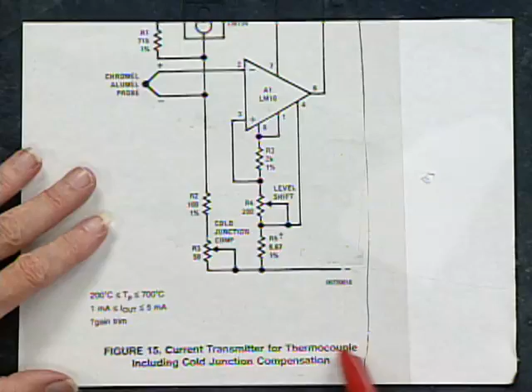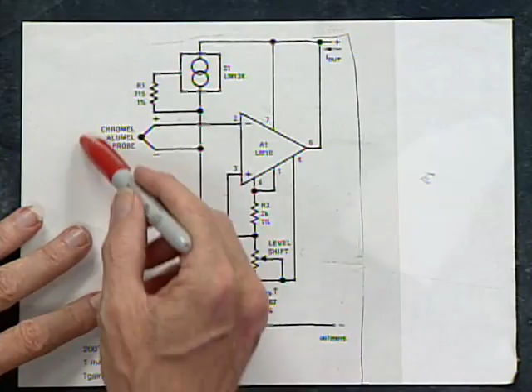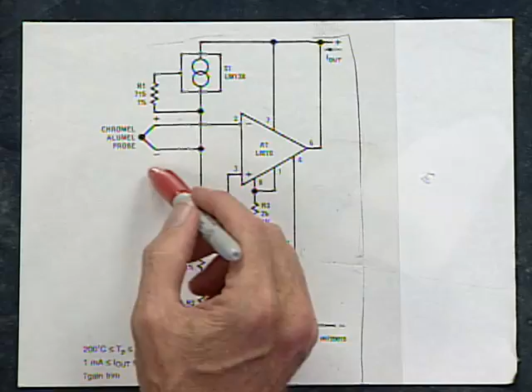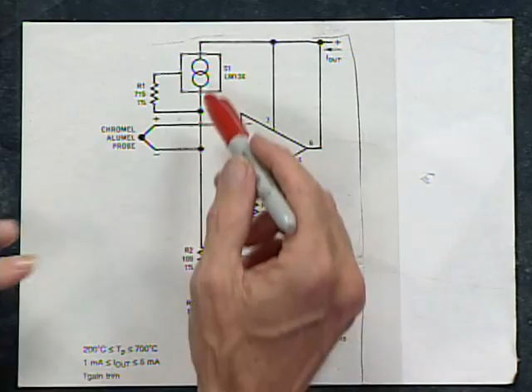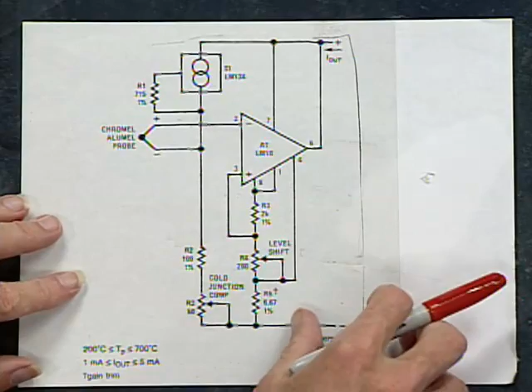Here's a current transmitter for a thermocouple, including cold junction compensation. You put a thermocouple into an op-amp and it can tell you the difference between the hot junction and the cold junction, but not what the cold one is itself. This provides cold junction compensation with the LM334, a temp sensor, with cold junction offset and level shift.